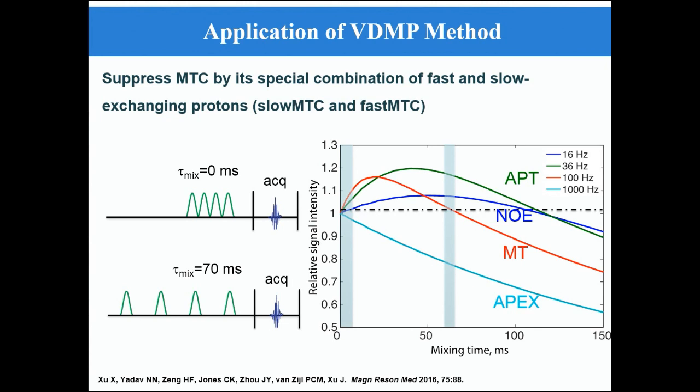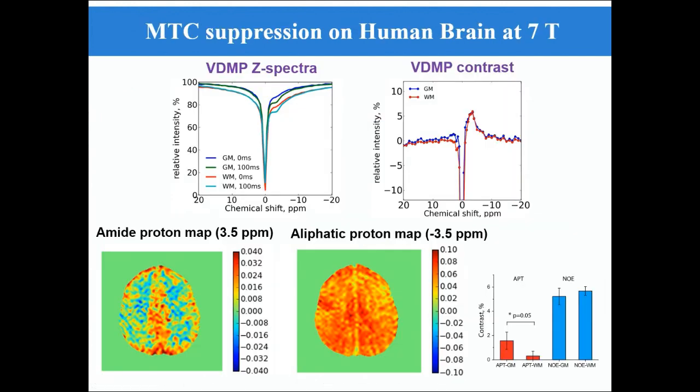First, the VDMP method can be used to suppress the MTC contribution. Because the MT pool contains fast and slow exchange components, the VDMP build-up curve is very unique. By taking the images with the mixing time where MTC has equal contributions and then subtracting these images, the contributions from MTC can be removed. Here are the results on human brain at 7 Tesla. We acquired a VDMP Z-spectrum with mixing times of 0 and 100 milliseconds. Then we subtract these two Z-spectra and obtain the CEST contrast without MTC contamination. Using this strategy, we can obtain pure amide proton and aliphatic proton maps.